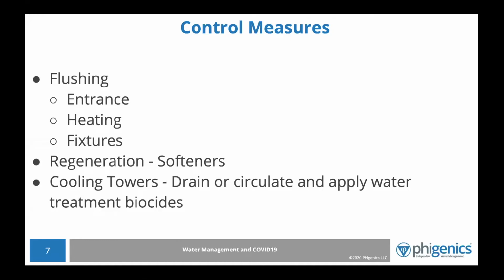Fixtures, again, flushing, those are all control measures. Something we see often in facilities with low use is softeners. If they go offline and sit stagnant, you're going to need to go in there and manually regenerate to keep the bed from fouling and becoming basically loaded with bacteria and injecting into your system. So you may want to go from a flow-based regeneration to a time-based regeneration. Cooling towers, again, holding time like heating hot water. You may not call because you're not evaporating, but you're going to want to drain a small amount of water if you're leaving water in those cooling towers so that your holding time doesn't go over 3 or 4 days.